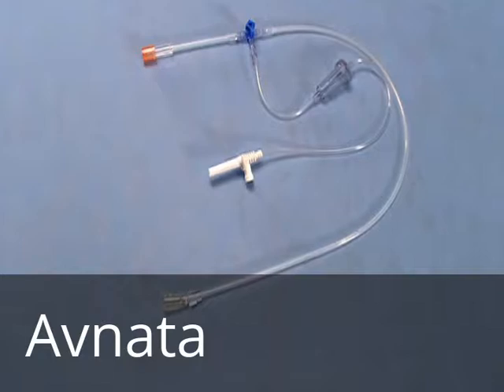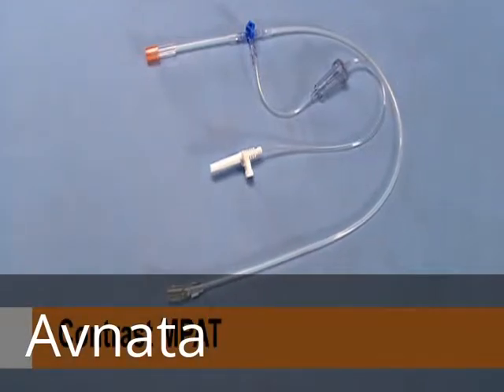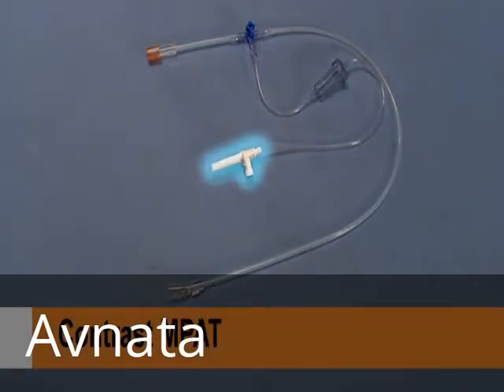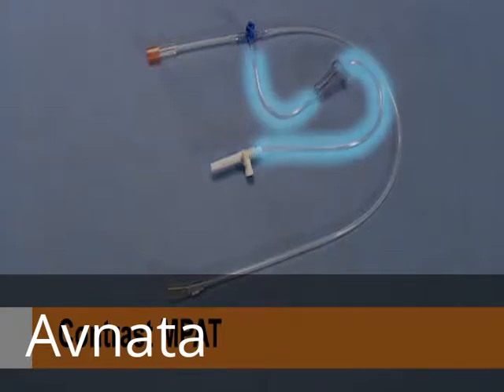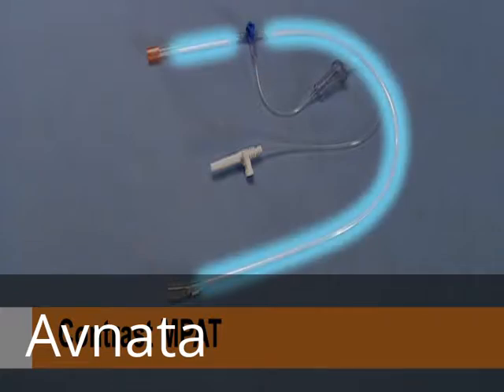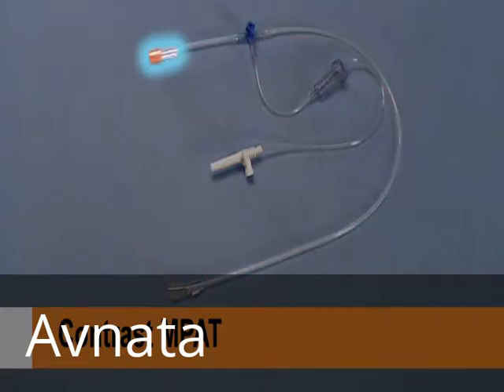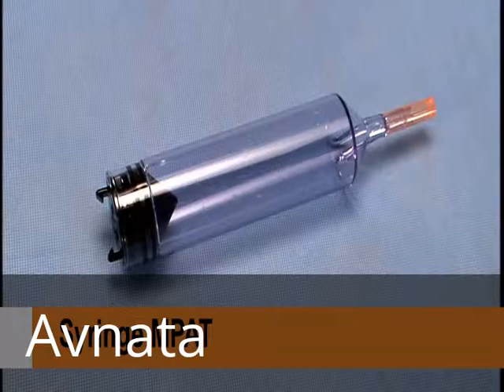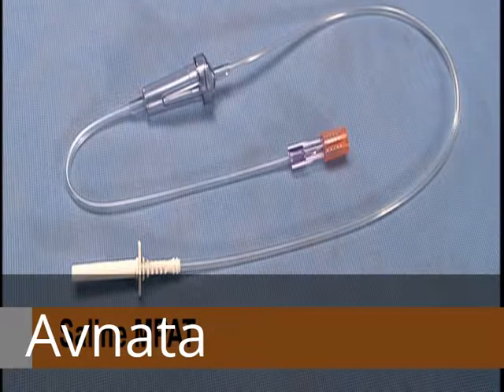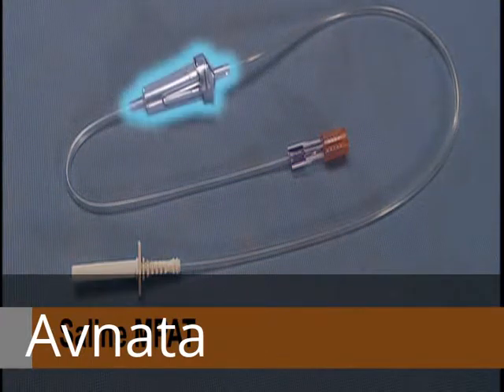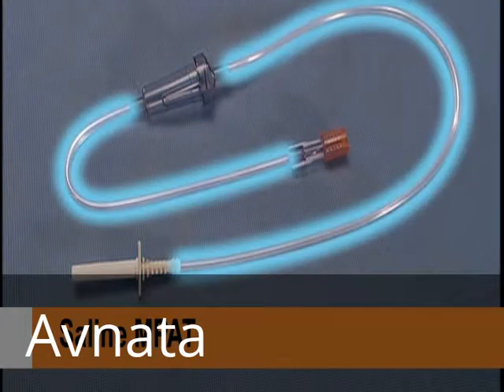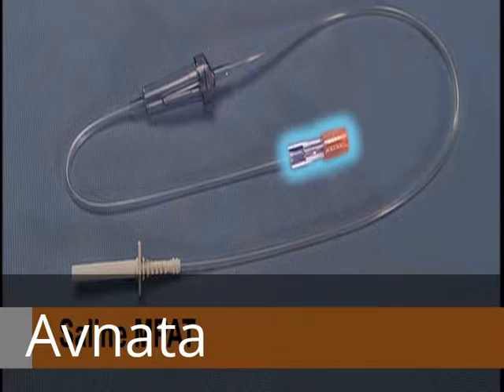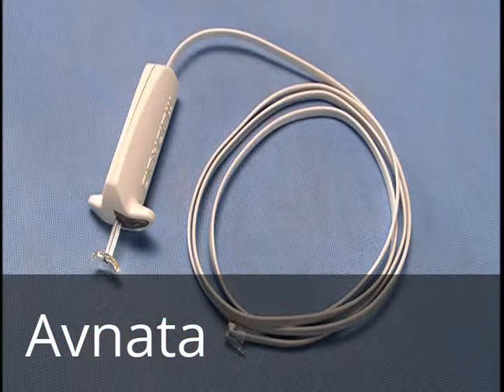The MPAT disposable set for the contrast component includes the vented contrast spike, low-pressure contrast tube, drip chamber, contrast flow control stopcock, high-pressure contrast tube with male luer connector, and a 150 milliliter multi-patient syringe. The saline MPAT consists of a saline spike, drip chamber, high-pressure check valve, and low-pressure saline tube with female luer connector. The hand controller is used to deliver both contrast and saline.